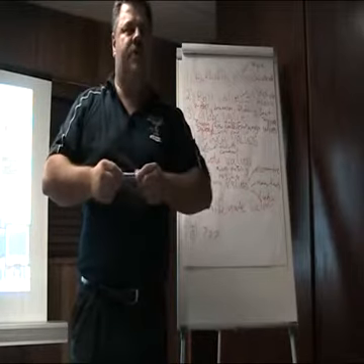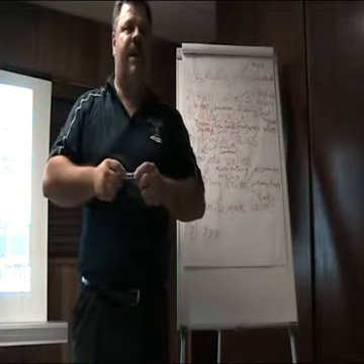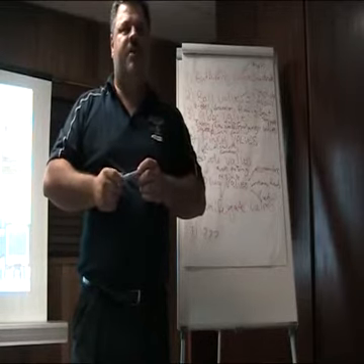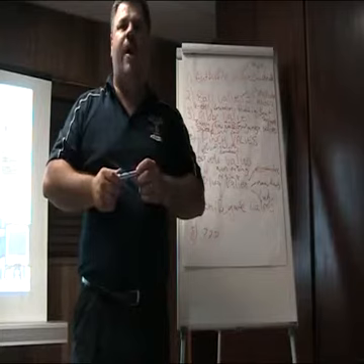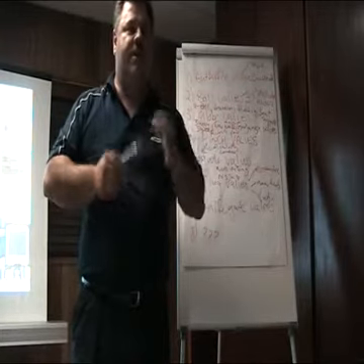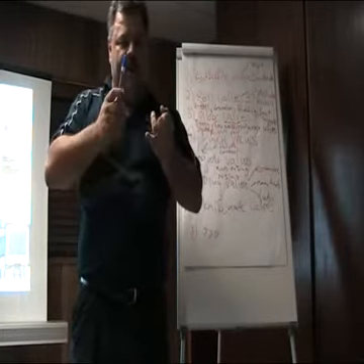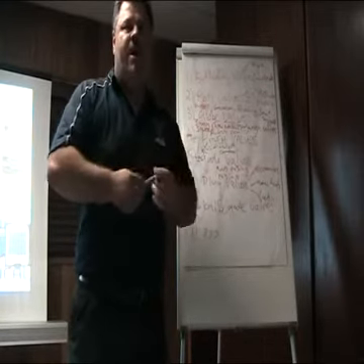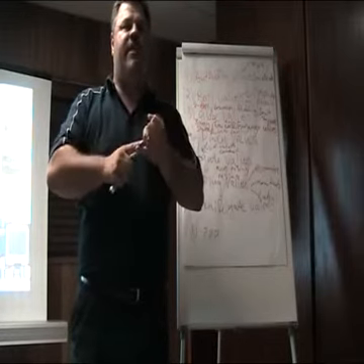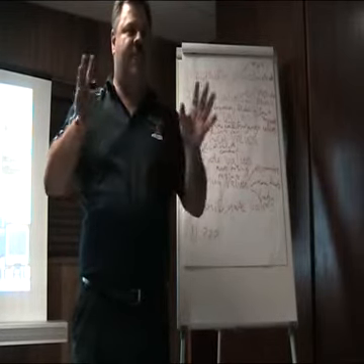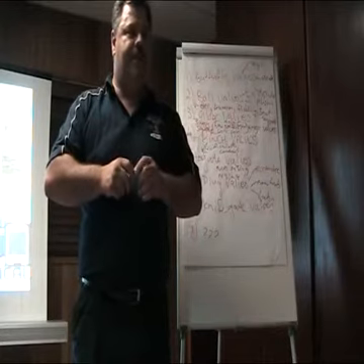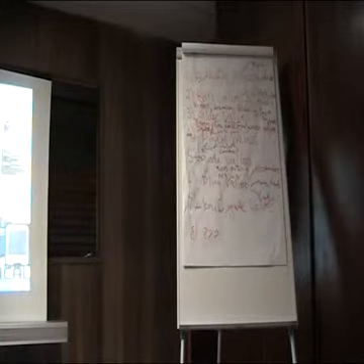So you usually use this. I've got an order now for about 90 of these valves, which is going to Angola for iron ore. Remember, knife gate valves are low pressure, low temperature as well. This is also the valve that they use a lot in mining. If you talk butterfly valves, you talk knife gate valves, mining industry a lot. You normally have a rubber seat, not a high temperature thing with a metal seat, and you get a through gate as well.